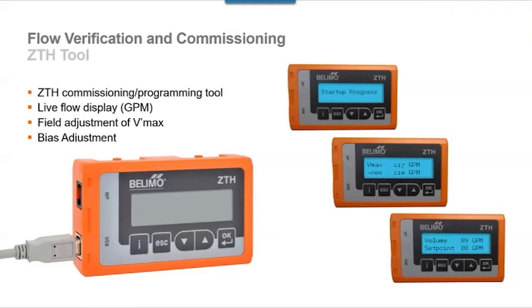The ZTH tool that you see here, and just a couple of pictures of it to show you, as I said, tells you what that programmed Vmax setting is. You can adjust it. You can tweak that flow to where you want it. It will also tell you the flow as read by the flow meter and what the set point is.